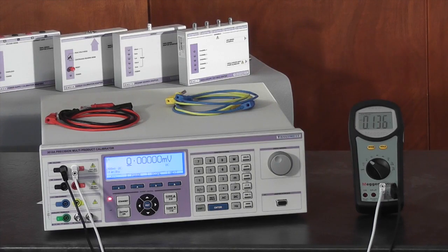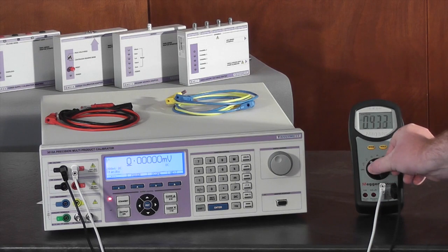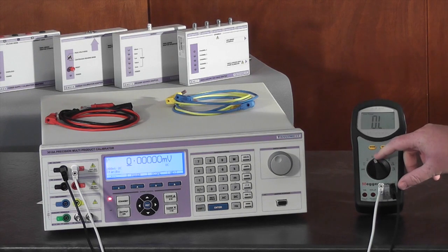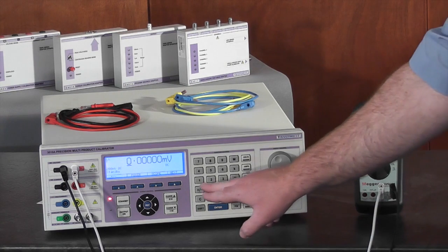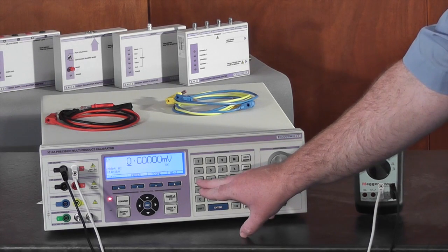Sourcing resistance from the 3000 series calibrator can be done as either 2 wire or 4 wire passive and simulated resistance. Passive resistance offers the best accuracy. First, switch the multimeter to the ohms mode and enter the required test value, for example 100 ohms.